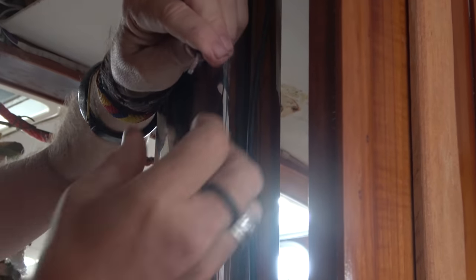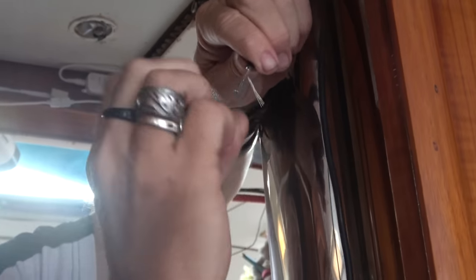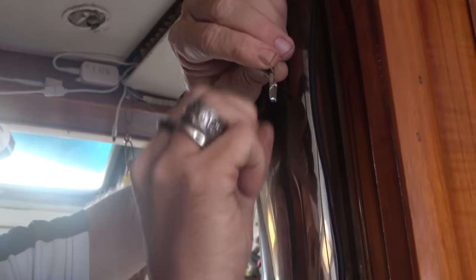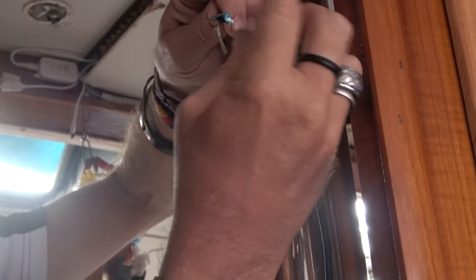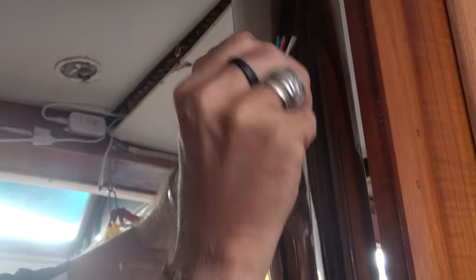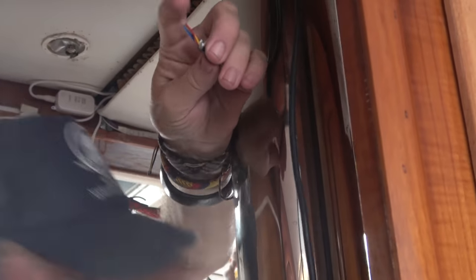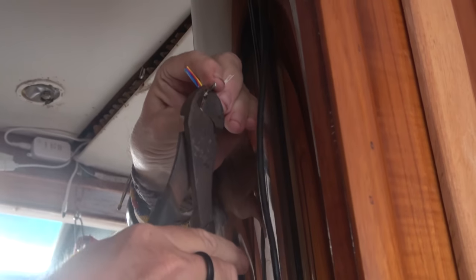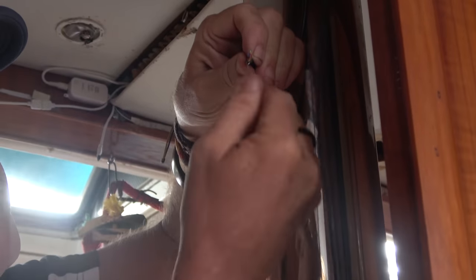Wire casing comes off. The shield is left fully intact. You can see here is our copper stranded shield wire there. And we also have this foil shield, which encapsulates the entire wire. So we're going to twist back the foil shield and take that off. We don't need the foil at this moment. And we twist together the shield wires.